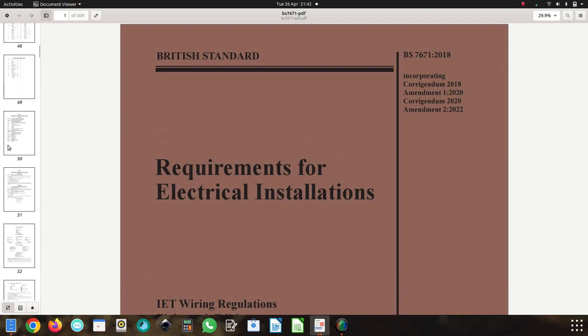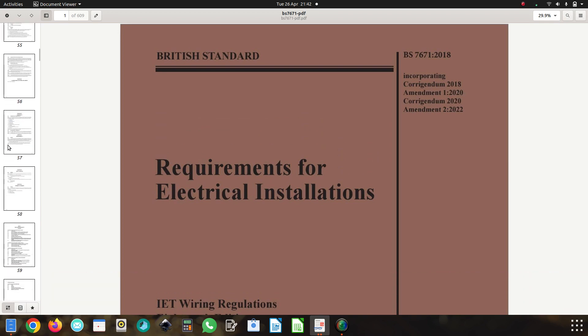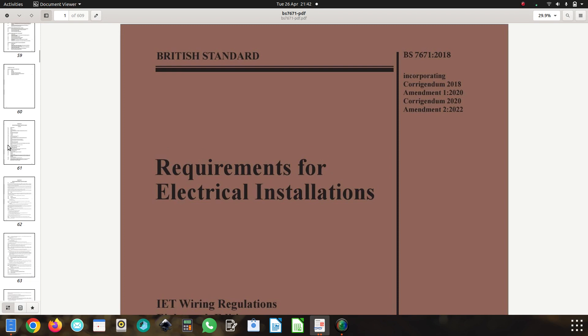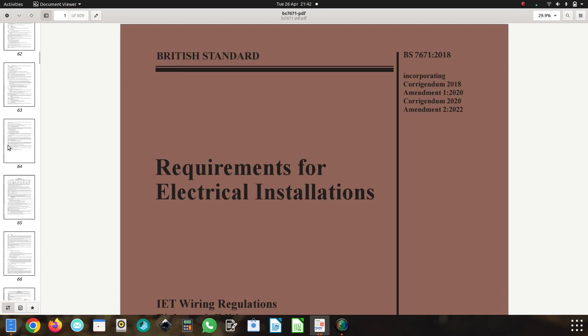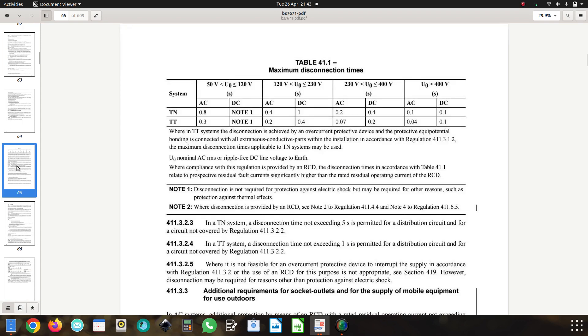Now if we have a look at page 65, which shows us the disconnection times in table 41.1, we're required to disconnect TT installations for final circuits in 0.2 of a second, and that's 120 to 230 volts U0 line to earth, so on single phase installations here.